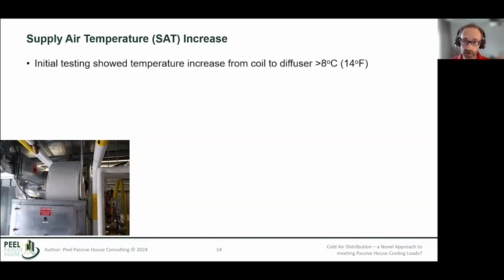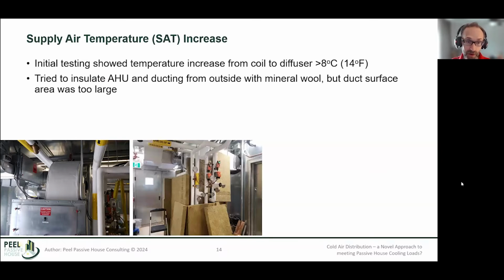One of the initial things I struggled with was a major temperature increase from the coil, measuring the temperature off the coil to at the diffuser, seeing about a 14F temperature increase. That was over maybe an 8-10 foot section of duct, not very long, thinking it goes direct into the room. So with very small amount of insulation on the duct, I decided to super insulate it, building a shield wall of mineral wool around the ducts, the fan coil unit, and so on.